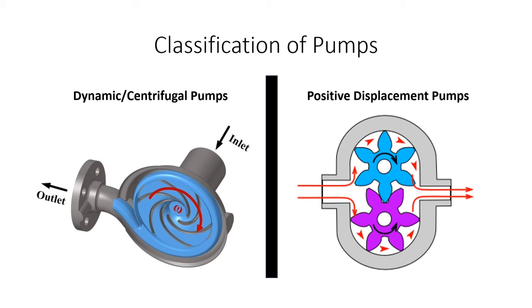Now let's categorize pumps into two main types: dynamic pumps and positive displacement pumps. Dynamic pumps, also well known as centrifugal pumps, impart velocity and pressure to the fluid as it moves through the pump impeller, and subsequently convert some of that velocity into additional pressure. Positive displacement pumps move fluid by trapping a fixed amount and forcing that trapped volume into the discharge pipe, delivering a fixed volume with each cycle.